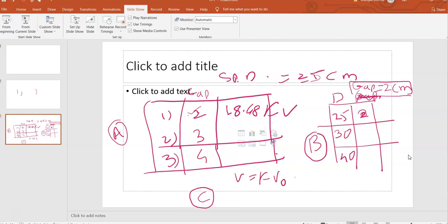So we will find out V, then find out V dash RMS value, and check that RMS value with the measured voltage. Then we can say yes, sphere gap can be used for measurement of high voltage. This third part we will see in the next practical, and problems will be asked: if observations are given to you, you will be asked to do the calculations. So you just see how to proceed from gap distance to voltage, applying correction factor K and finding delta, which will be required to solve the problem.